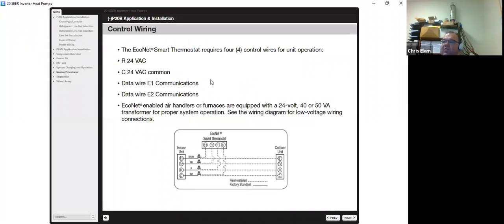The new EcoNet thermostats will actually have 6 terminals on it. You have an R and a C. Your R is your 24-volt power. Your C is your 24-volt common. You'll also have an E1 and an E2. Those are your DC communication wires. On the thermostat, you'll also have an S1 and S2. That gives you the option to run a remote sensor as opposed to using the actual thermostat as your sensing element. As you can see here, basically you have your E1, E2, R and C, and the same corresponding codes on the indoor and the outdoor unit.